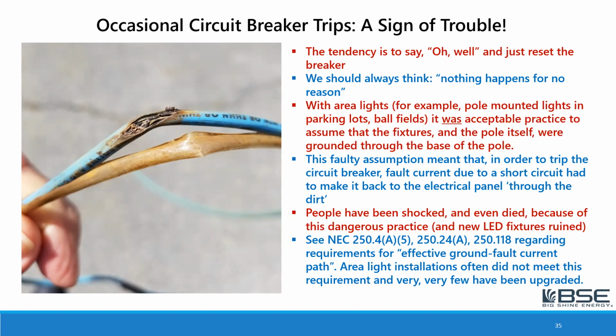But we really should think nothing happens for no reason. So if there's an occasional circuit breaker trip and you don't have a reason why it happened, it's really worth taking the time to investigate. I want to talk specifically about area lights because there is a problem. Mike Holt, the electrical code expert, has spoken very passionately about this issue.